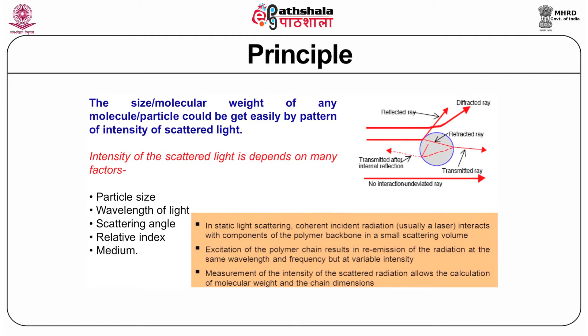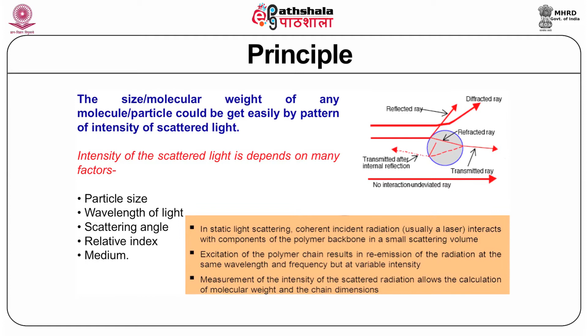Now, we talk about the fundamental principle of static light scattering. The simple principle is that the size or molecular weight of any molecular particle can be determined by the pattern of intensity of the light that you get after measuring static light scattering. The intensity of the scattered light mainly depends on five different factors. These are the particle size, wavelength of the incident light, scattering angle, refractive index, and the refractive index of the medium.